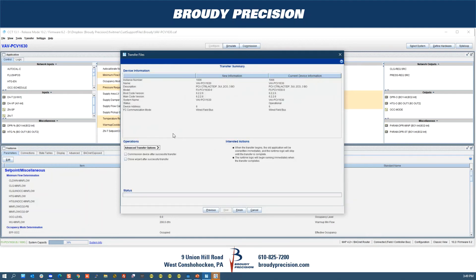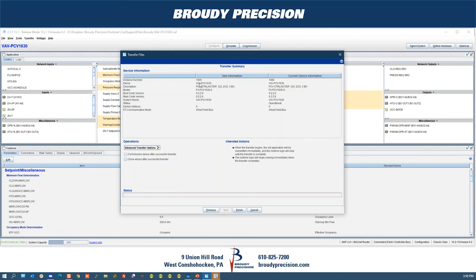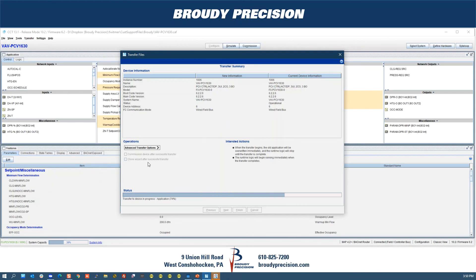This could be a direct connection to the JACE, or you could be out on the internet connecting to a job from your office if you have the ports forwarded — you can even handle main and boot firmware from there. In this case, all we want to do is a download, so we'll say Finish, and it's going to go through and download the application. The big thing is that you have the UDP port forwarded if you want to do this remotely, and once that's done you should have no problem connecting and working remotely to commission, upload, download, or do whatever you need with your controllers.